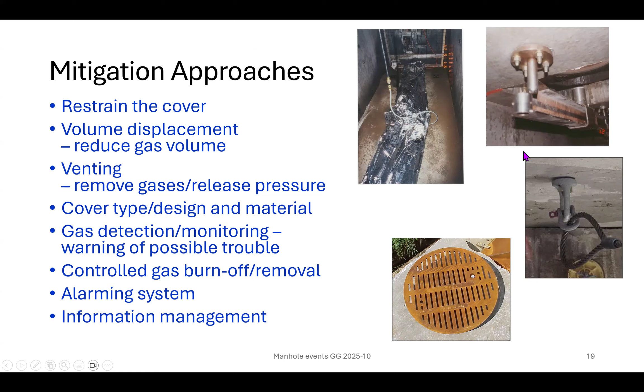Something like this, a plate that would prevent the cover, that would redirect the gases in some other direction, and maybe prevent the gases from escaping. We had some doubts about this, but we tested it, and what we found is that this steel plate, which was suspended from the frame, would just be pushed into the frame and block the entire cover frame. So the gases had no place to escape and would rip the whole thing apart.